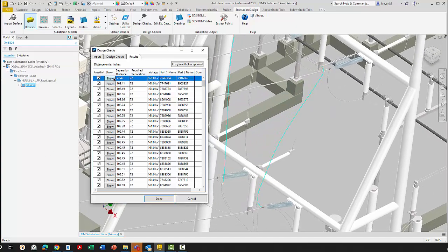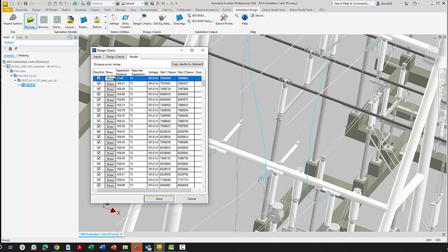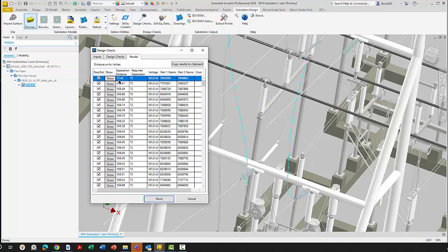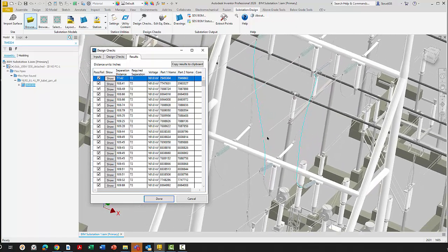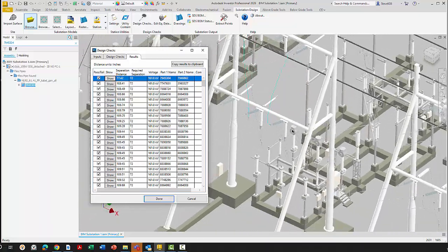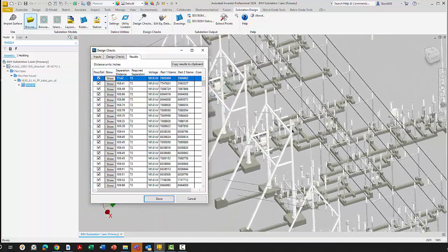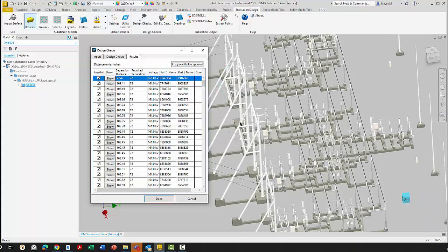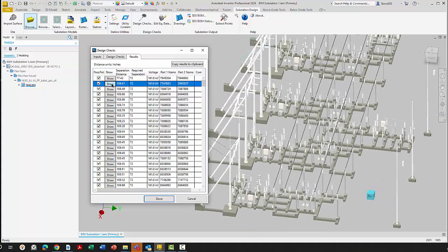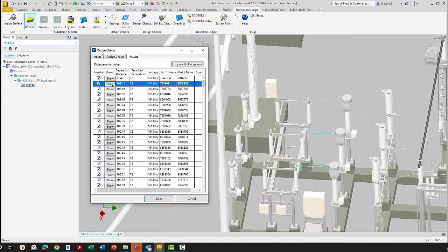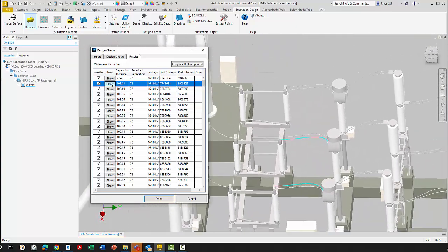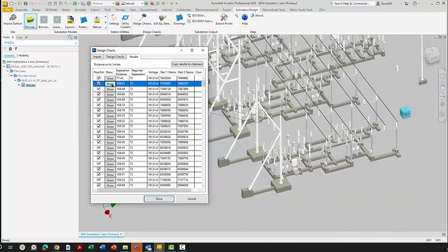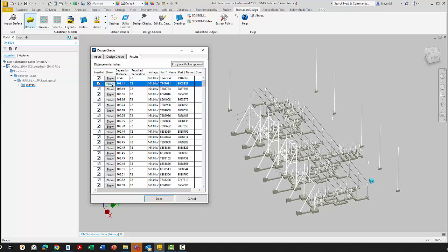You can see these two phases are a little bit close - 77. So we want to make sure that we have those cables trained so they don't have interference by chance three or four inches here. I don't know how much they're going to wave around in the weather. So we can see that those two pass. If we want to look at any other ones, I can see it highlight and you can see those two are checked. It's going to look at phase to phase throughout the whole model. Everything passes in this. We expected them to pass, but it's good to check. You can copy to clipboard and otherwise, we're done.